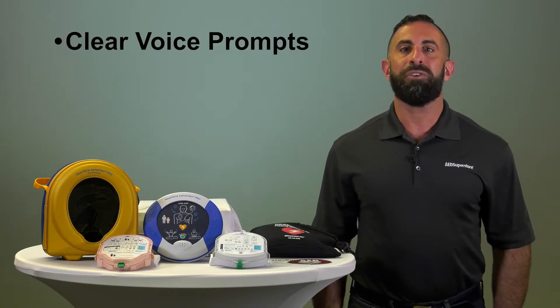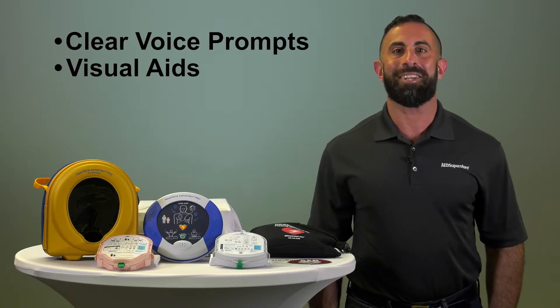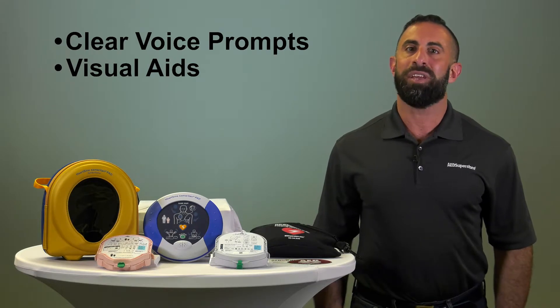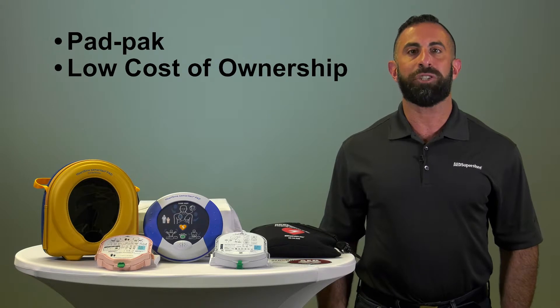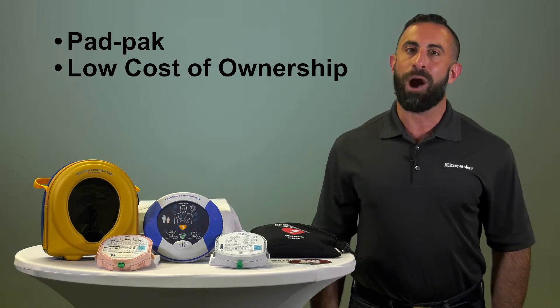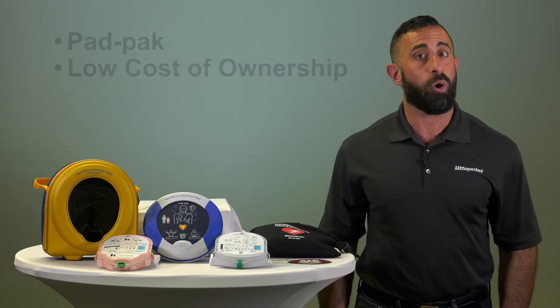Both devices are easy to understand and use clear voice prompts as well as visual aids that guide the rescuer through the entire process. The 350 and 360p use an electrode pad and battery combination called a Pad-Pak. The Pad-Pak has a four-year shelf life with over six hours of continuous monitoring or 30 shocks.